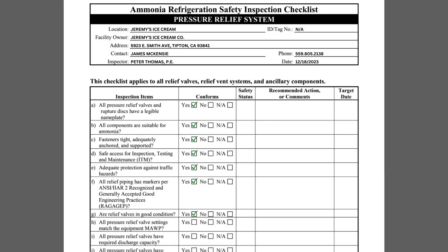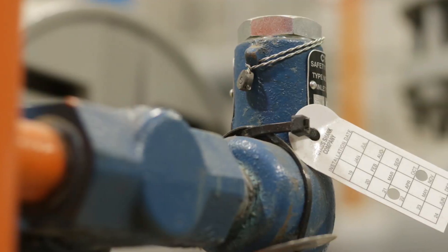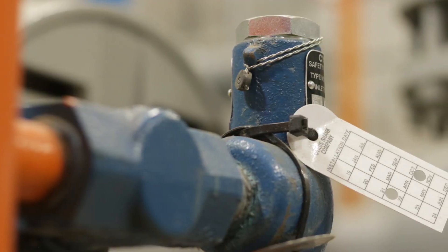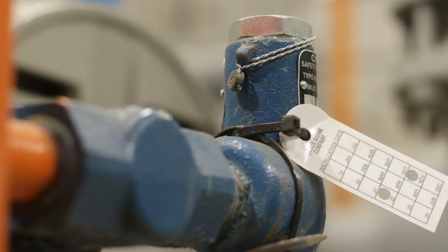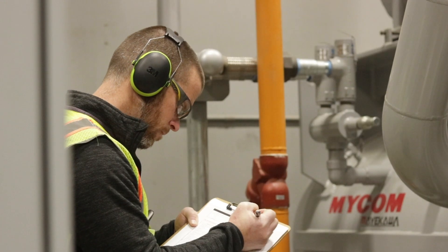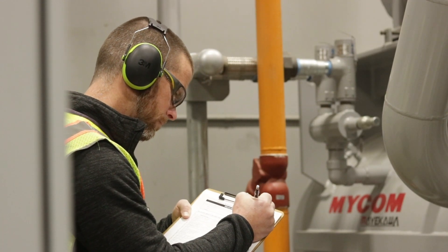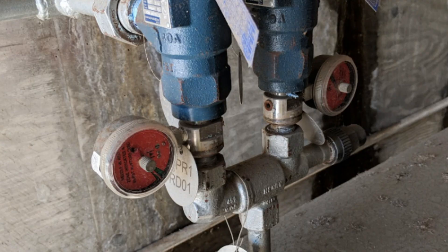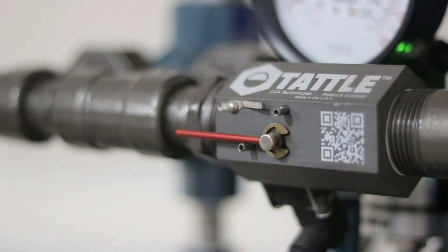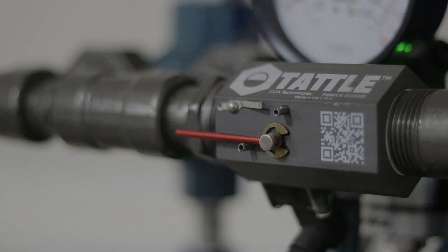Item G asks if the relief valves are in good condition. Inspectors should look for corrosion, excessive dirt buildup, or cobwebs to ensure the system is being properly maintained. If the relief system has instrumentation to detect when a relief valve lifts, such as a rupture disc, pop eye valve, or tattle, ensure the device is not indicating that the relief valve has lifted.